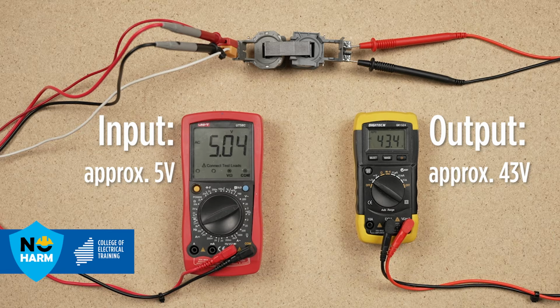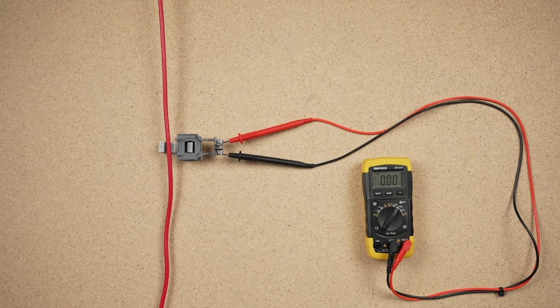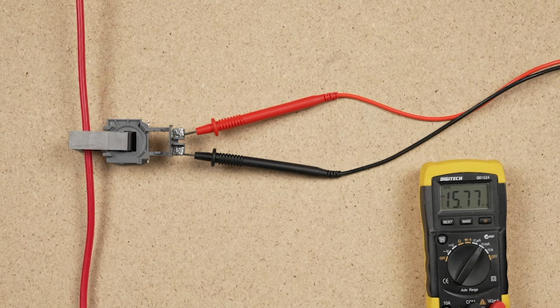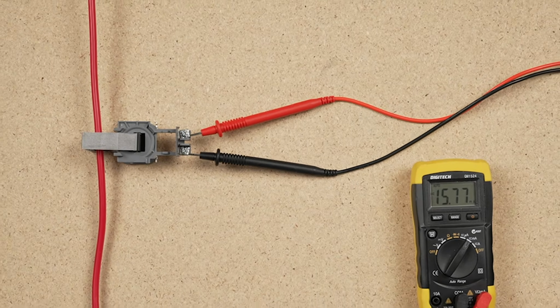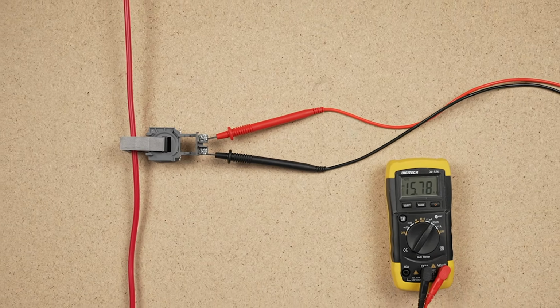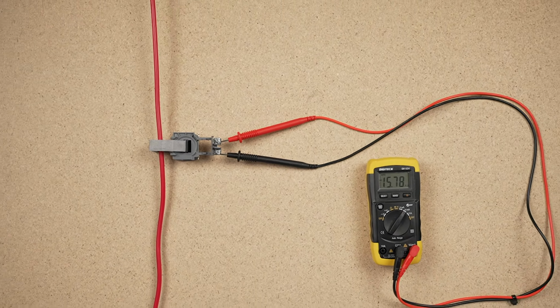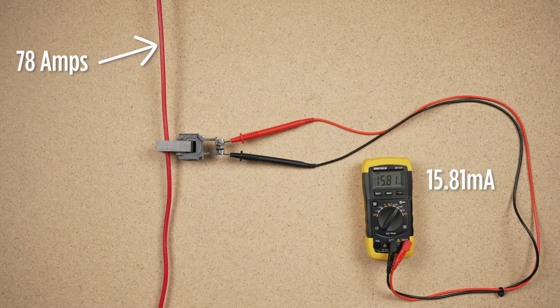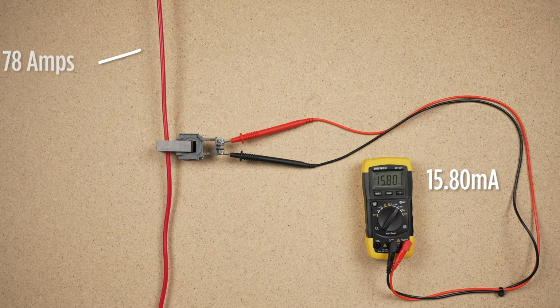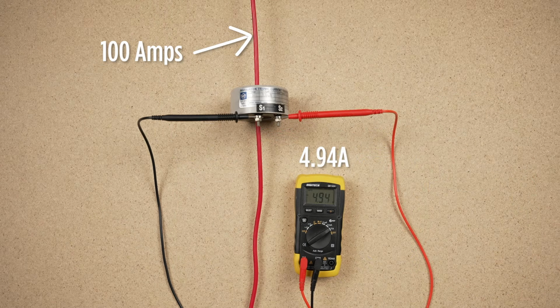primary input voltage. Current ratios in a transformer are inversely proportional to voltage ratios. This is also true for current transformers. So the secondary current of the CT will be significantly less than the primary current of the conductor being measured. Examining the design of the current transformer, we observe that the primary winding of the CT is made up of a single conductor, such as a cable or bus bar, which passes through the toroidal core of the CT once. Here we see the real CT set up for operation.